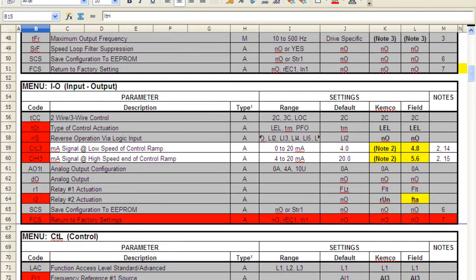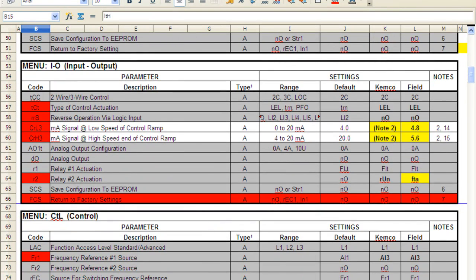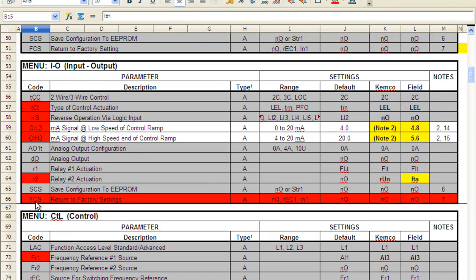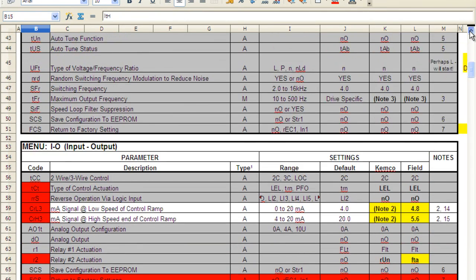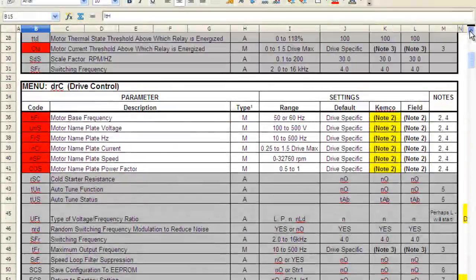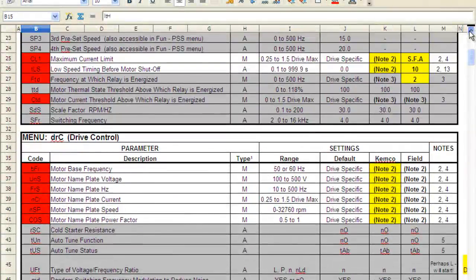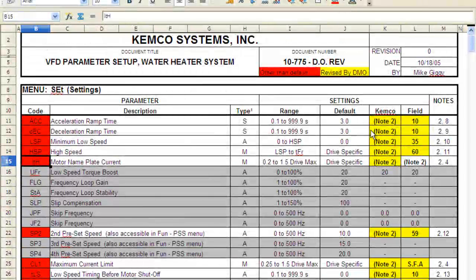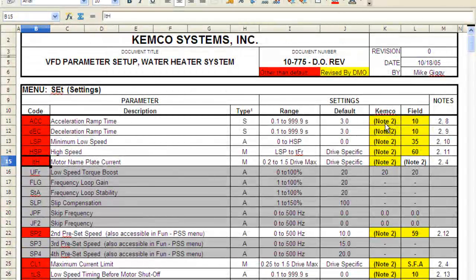If somebody's been into the drive and you're cleaning up after somebody, if you have multiple shifts, this parameter here, navigating through and changing to factory defaults, this will put all parameters back to factory defaults. Then you will have to go into the drive and change all the red things to what they should be, based upon the yellow permissives here, and sometimes also associated with a note.